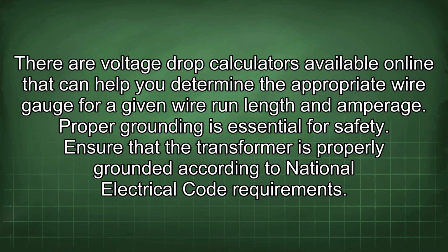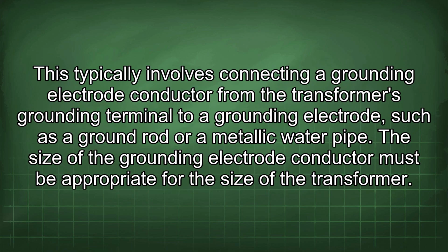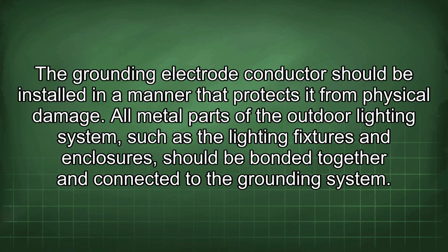Ensure that the transformer is properly grounded according to National Electrical Code requirements. This typically involves connecting a grounding electrode conductor from the transformer's grounding terminal to a grounding electrode, such as a ground rod or a metallic water pipe. The size of the grounding electrode conductor must be appropriate for the size of the transformer. The grounding electrode conductor should be installed in a manner that protects it from physical damage.